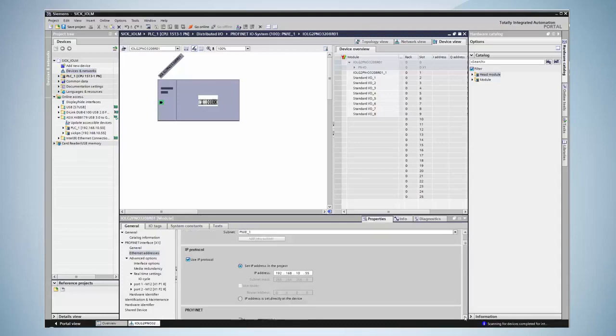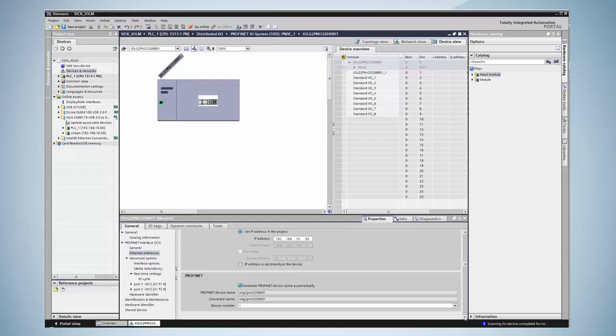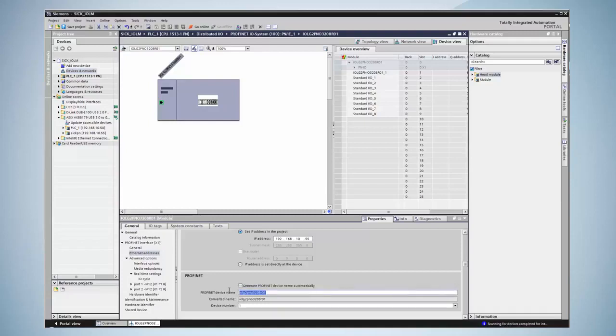The next important step is the PROFINET name. The PROFINET controller assigns an IP address via the device's name. In this field the name that has been determined before will be entered. In this example it is SICK-PN.